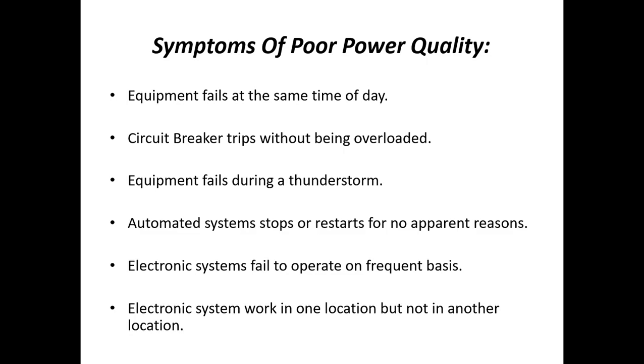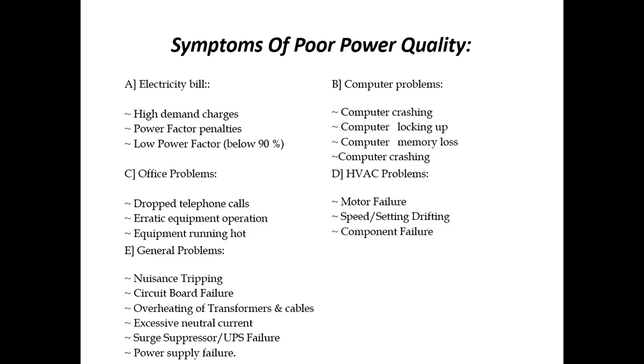So electronic systems fail to operate on a frequent basis. That means there are some power quality issues such as voltage sag, voltage swell, harmonics, transients, short duration voltage variation, and long duration voltage variation. If all these power quality issues are there, then the electronic system fails. So an electronic system works in one location but not in another location. So these are some symptoms of poor power quality.